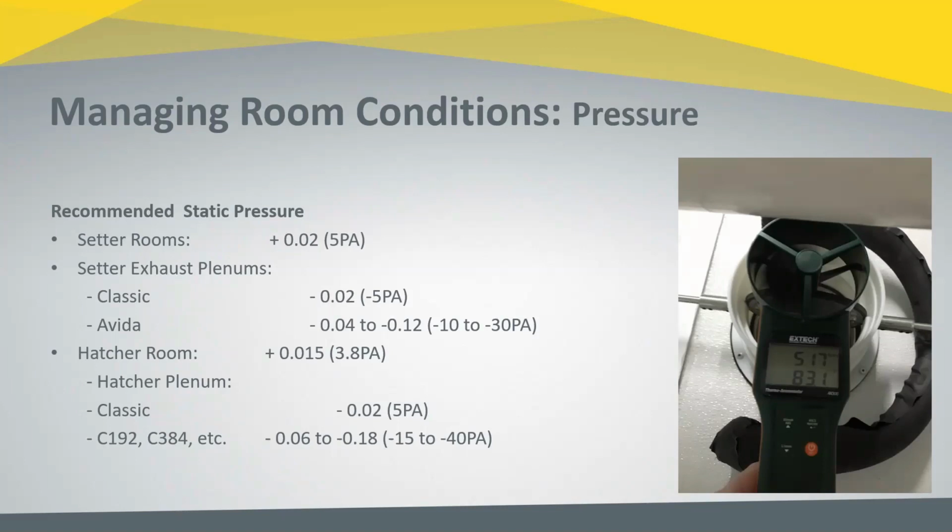Robert says, we have trouble with fluff buildup clogging the cooling coils on the hatchers. Is this a water temperature or pressure issue, or a static pressure issue, or both? Yeah, it can be a combination of multiple things. One being the pipping process produces a lot of moisture in the hatcher machine. And with that moisture at that specific temperature, generally in the neighborhood of 97.8, 97.9 at time of pipping, you can reach condensation dew point on your coils very quickly.